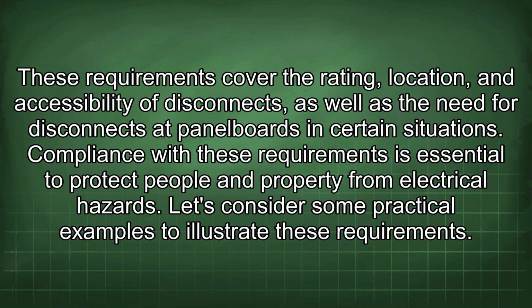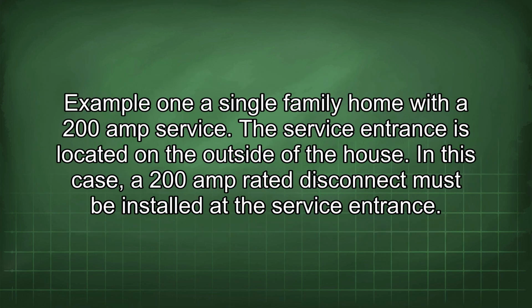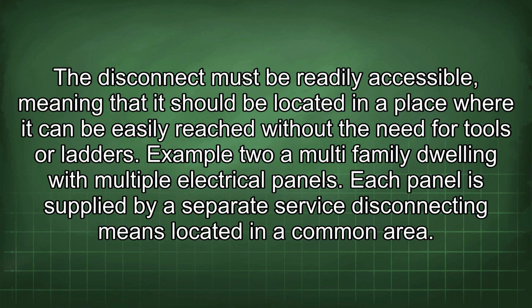Let's consider some practical examples to illustrate these requirements. Example 1: a single family home with a 200 amp service. The service entrance is located on the outside of the house. In this case, a 200 amp rated disconnect must be installed at the service entrance. The disconnect must be readily accessible, meaning that it should be located in a place where it can be easily reached without the need for tools or ladders.